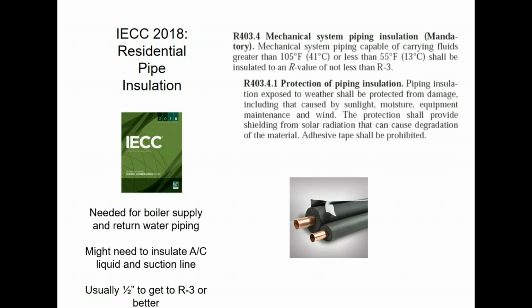My note on the left there says needed for boiler supply and return water piping. It probably should say needed for boiler supply piping if it's high temp, needed for return piping only on a snow melt system. I didn't do a good job with my notes on the left there. I apologize. A normal boiler system, radiant floor, radiator, baseboard, etc., you're not going to be below 55. Well, okay, let me step back. You're going to be above the 105. So let's just do it this way. My apologies. I'll make it real simple.